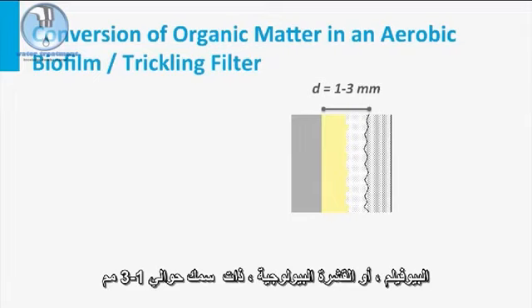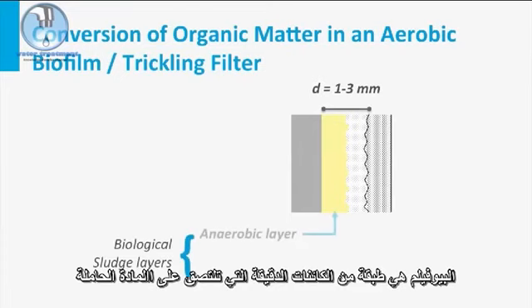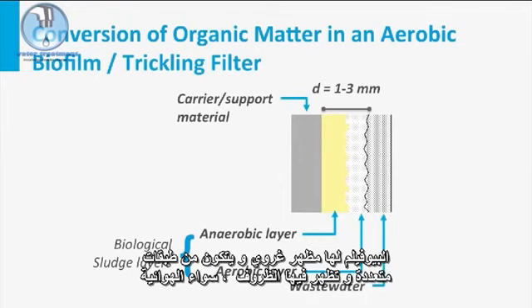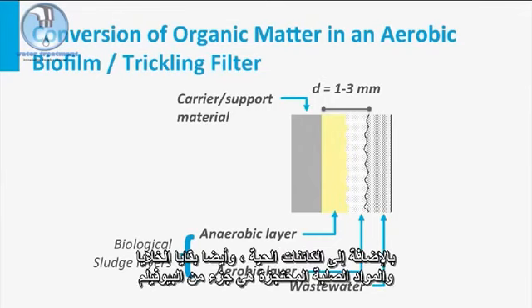The biofilm, or biological skin, is about 1 to 3 mm in thickness. The biofilm is a layer of microorganisms attached to the inert support material. The biofilm has a slimy appearance and consists of multiple layers in which both aerobic and anaerobic conditions appear. In addition to living organisms, also cell remainders and entrapped solids are part of the biofilm.